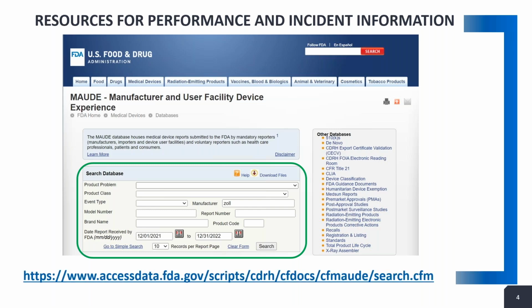So there's a link here at the bottom. If you want to copy the presentation, I'm happy to provide it for you. But it's a really good, useful database to reference if you want to know what's been happening with these kinds of devices in the field. And it's not particularly just defibs. It could be any FDA regulated device. So it's a good reference to utilize if you're having some issues with some particular medical devices. You want to know, okay, are other sites around the country seeing a particular issue? So it allows you to search by product type and name, and you can look at any and all reported incidents to the FDA.